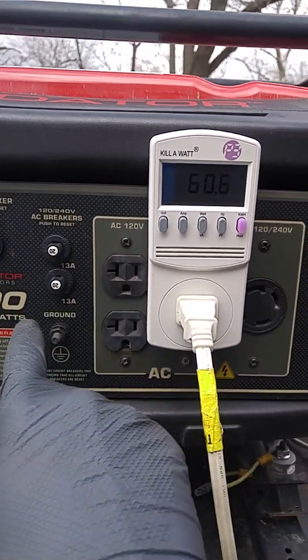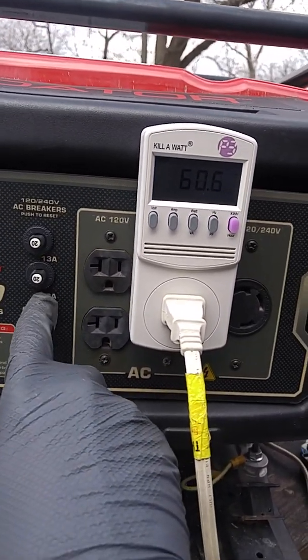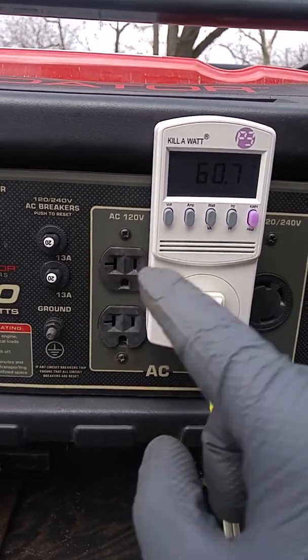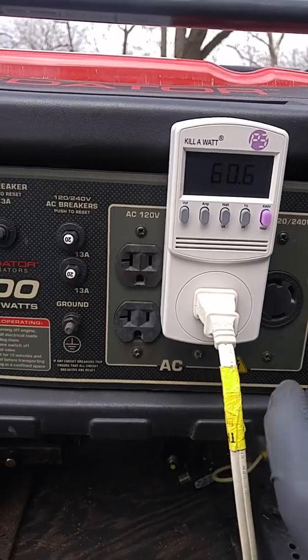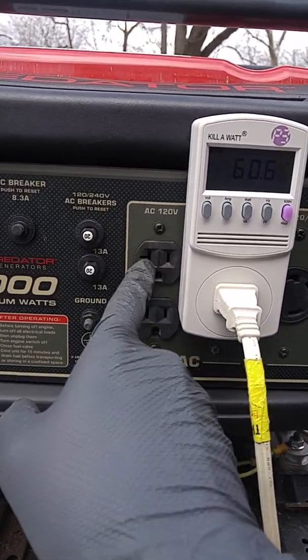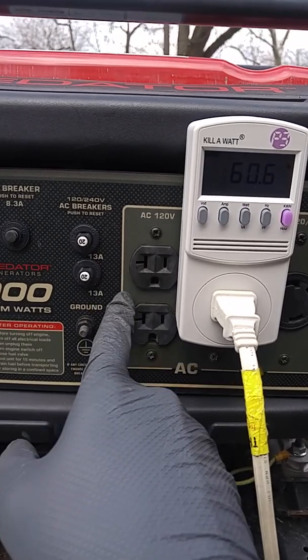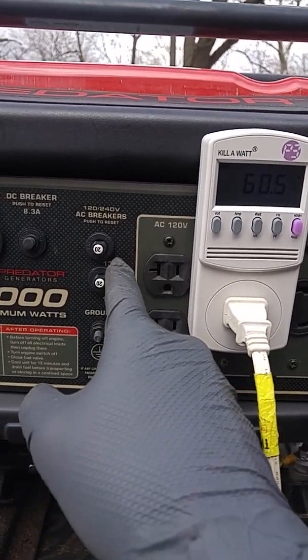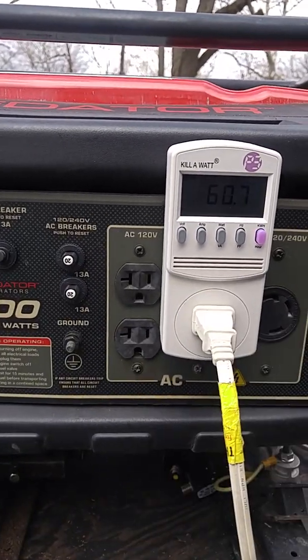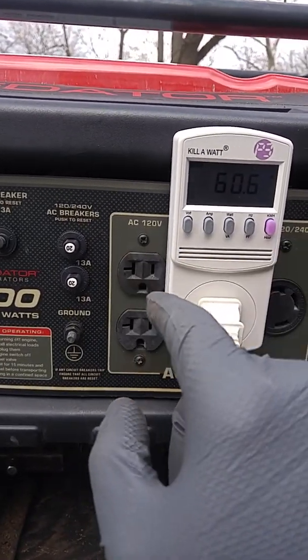I have room right here to put a 13-amp breaker — I'd have to wire that into the 240. I think that's correct for the 240. For the 120s, that's fine adding 20 amps. This will be 20 amps for each 120-volt leg winding.